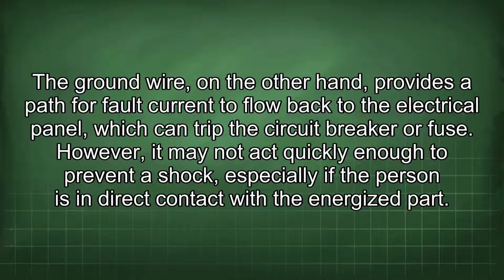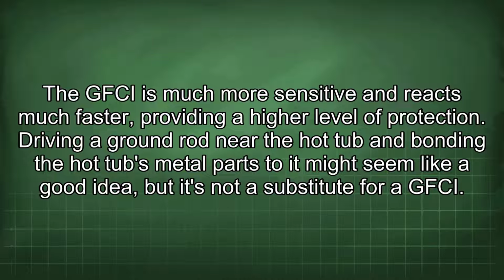The ground wire, on the other hand, provides a path for fault current to flow back to the electrical panel, which can trip the circuit breaker or fuse. However, it may not act quickly enough to prevent a shock, especially if the person is in direct contact with the energized part. The GFCI is much more sensitive and reacts much faster, providing a higher level of protection.